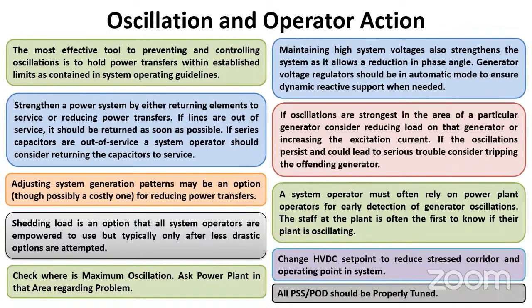So one more point: somebody has written about operational cost. I'll tell you how this operational cost can be defined: let's say a power plant can evacuate 500 megawatt, it has created a line, but due to low frequency oscillation, you have restricted it to 400 megawatt. Certainly the 100 megawatt can be quantified as its operational cost now.